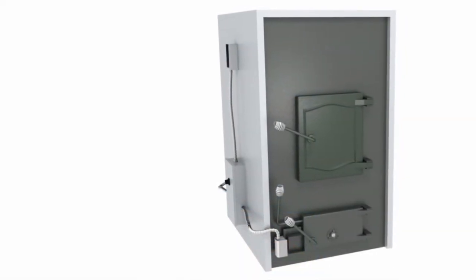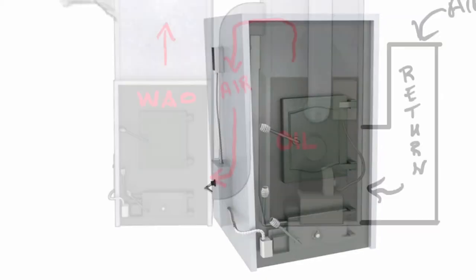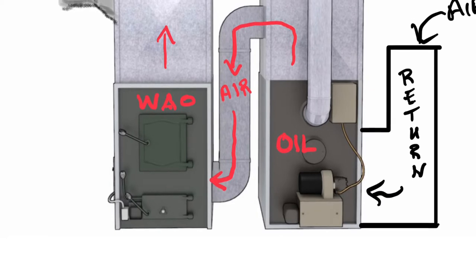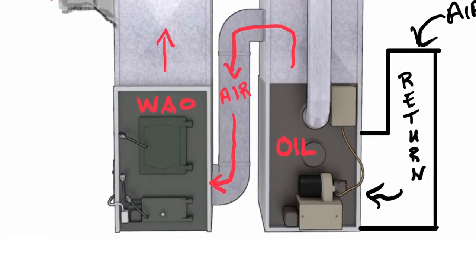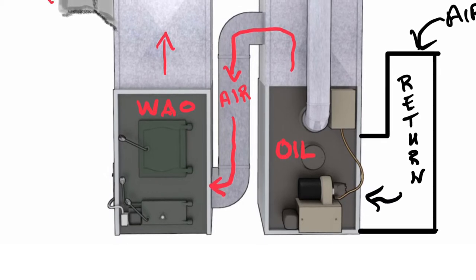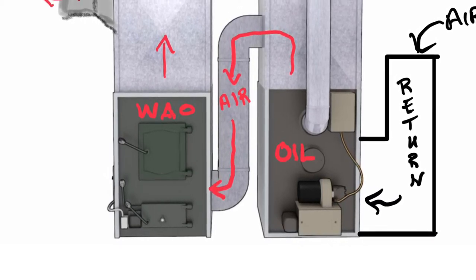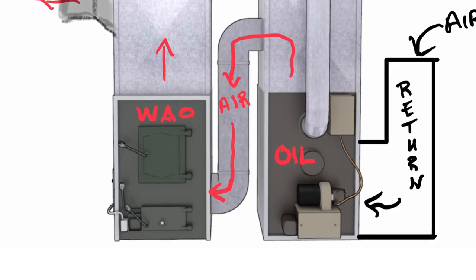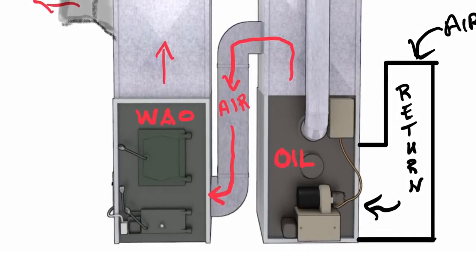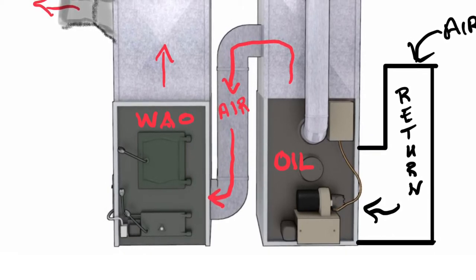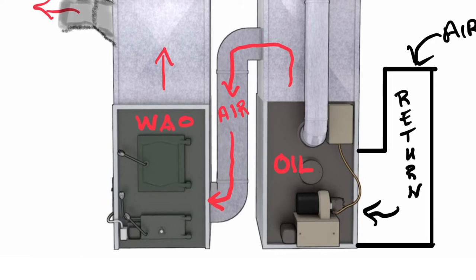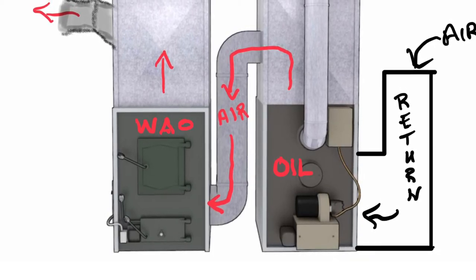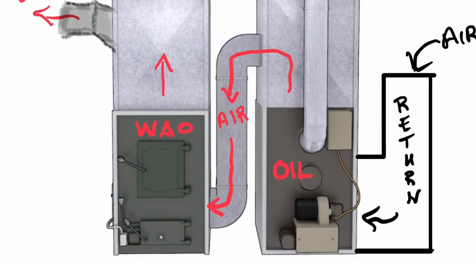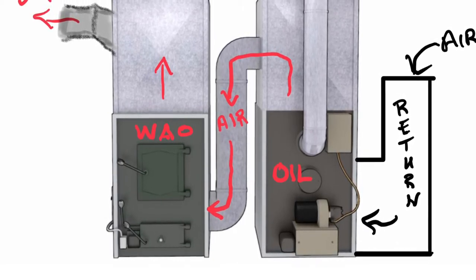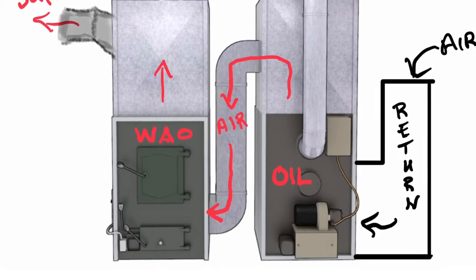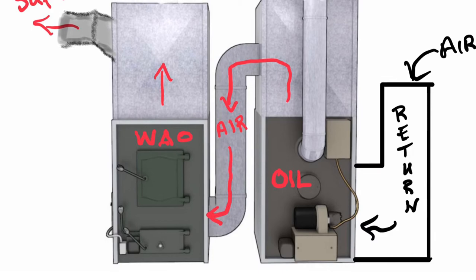This unit here is called a wood add-on. Because a wood add-on has no blower to get rid of the heat, it must be combined with another furnace with a blower. This example shows an oil furnace with a blower combined with a wood add-on. You can see that the air is going up the supply plenum of the oil and down into the wood add-on and up through its plenum. One of these units would be considered your backup unit, and it would require two thermostats, one for the oil and one for the wood add-on.